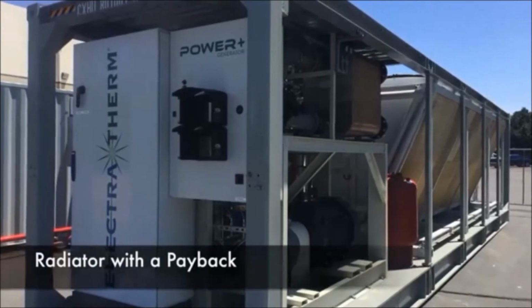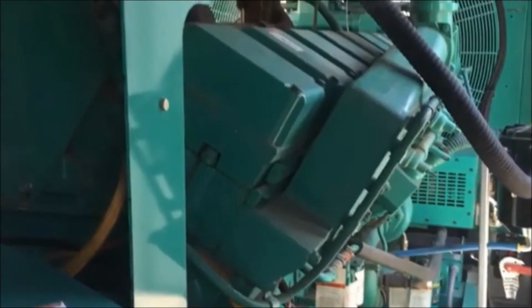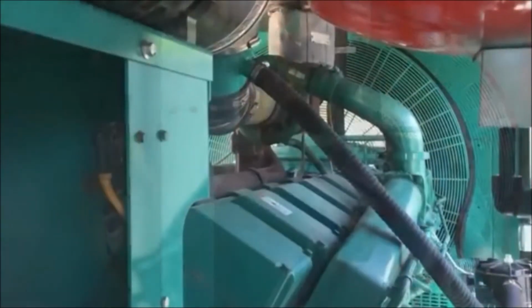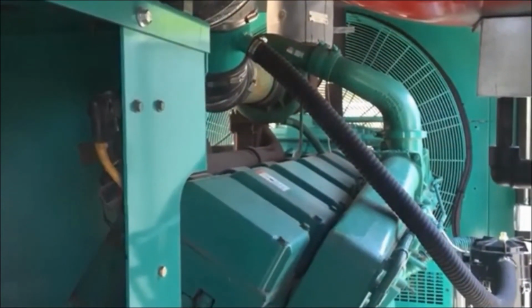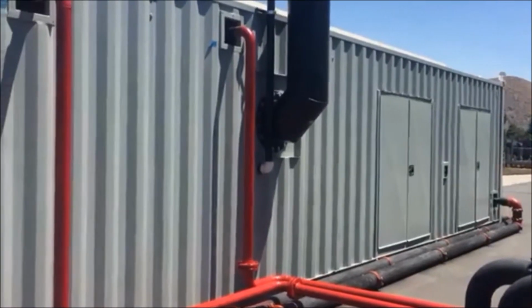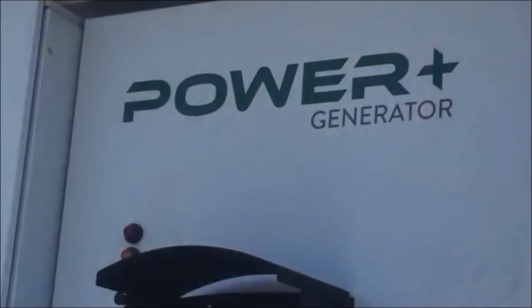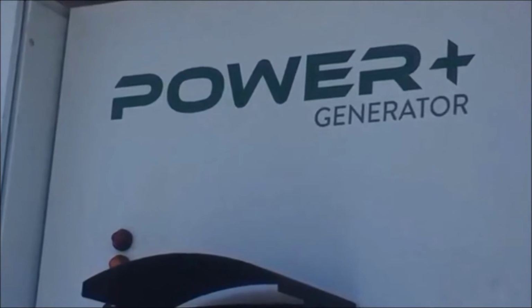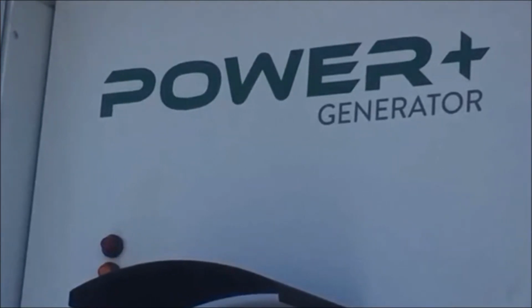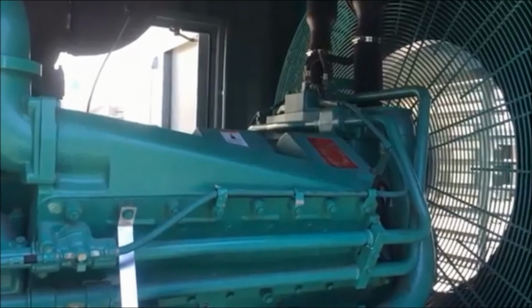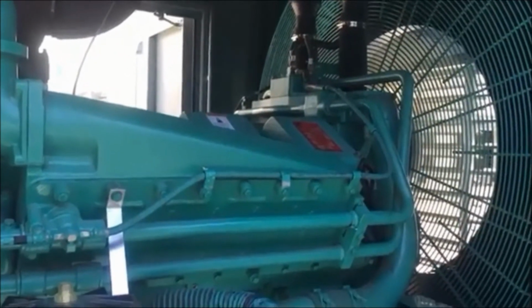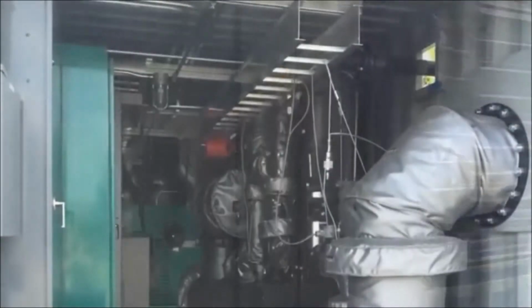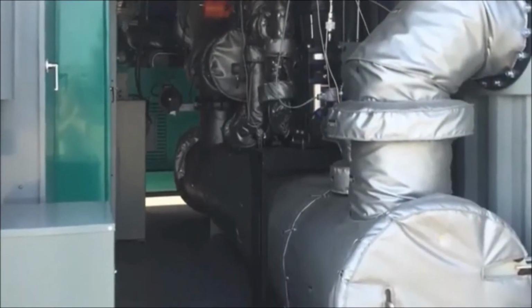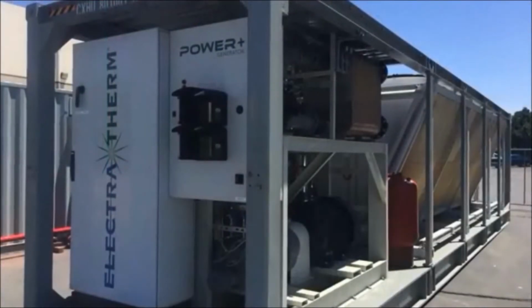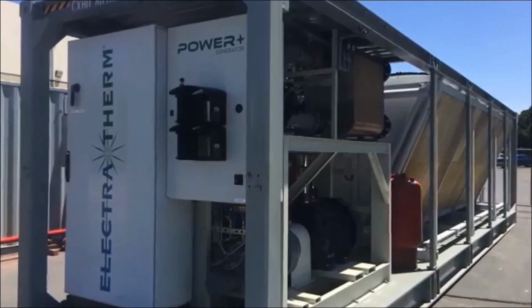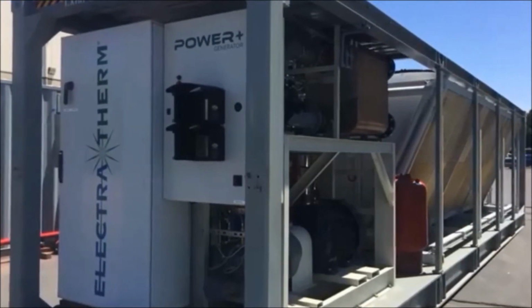The Cummins engine runs at approximately 35% efficiency, with considerable unutilized waste heat between the jacket water and the exhaust. By integrating ElectraTherm's Power Plus generator, the PTO-driven radiator is eliminated. The small fan in the back has no coil behind it and is only used to draw in combustion air. The waste heat from the jacket water and exhaust gas is diverted directly to the Power Plus. The Power Plus then produces power from the wasted heat and at the same time cools the engine.